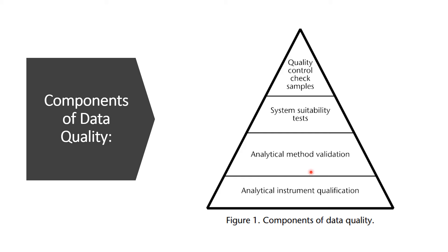Next is analytical method validation. Whichever analytical method you will use to analyze the samples, that method should be validated. The use of a validated procedure with a qualified analytical instrument will provide confidence that the procedure will generate test data of acceptable quality. Next is system suitability test. In the system suitability test, you verify that the system will perform in accordance with the criteria mentioned in the procedure. These tests are performed along with the sample analysis to ensure that the system performance is acceptable at the time of the test. For example, in the HPLC system, you use the SST solution to check the resolution, peak symmetry, retention time, and repeatability to ensure that the method is functioning correctly and consistently.